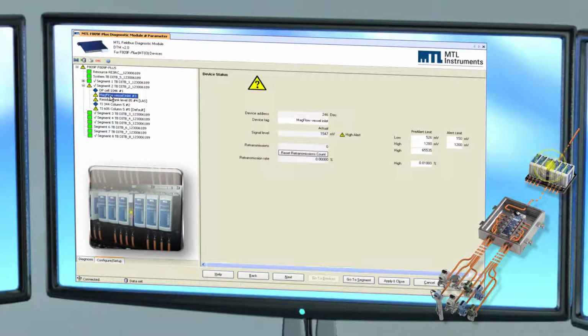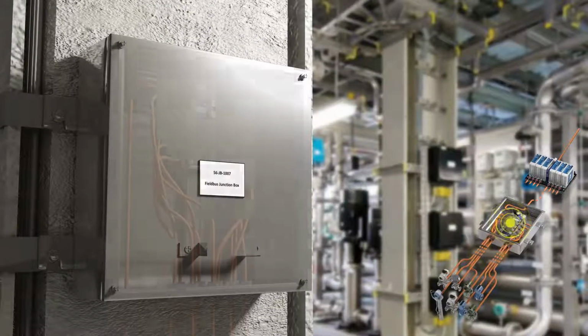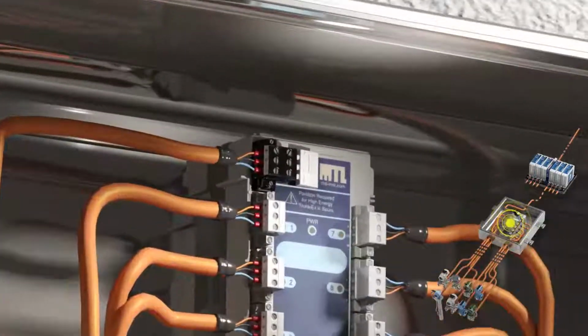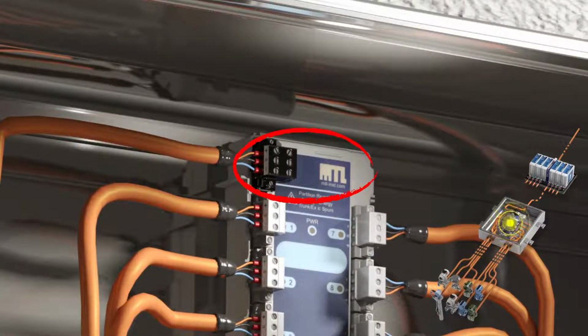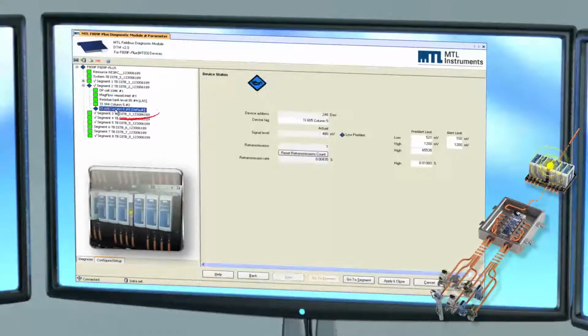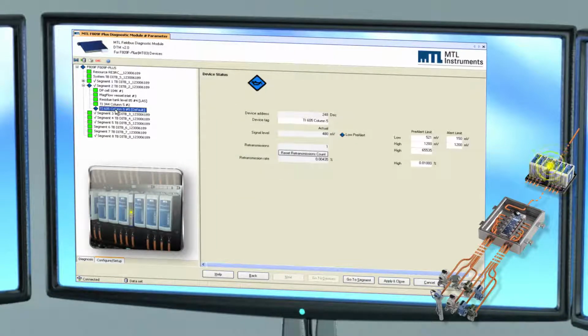If a terminator is missing from the segment, most likely at the device coupler in the field junction box, the signal level of all devices will exceed the pre-alert or alert limits on the affected segment. This measurement feature is ideal during the commissioning phase of a new Fieldbus installation, since the F809F+ automatically detects missing terminators. Here we see a low signal level on a single field device, indicating that an individual Fieldbus device or its spur connection are defective.